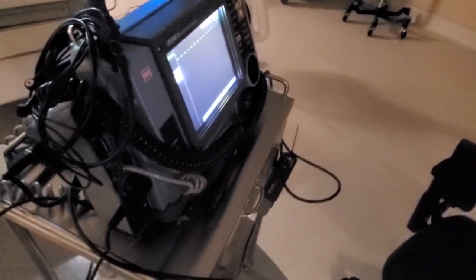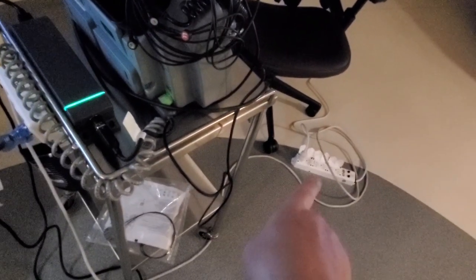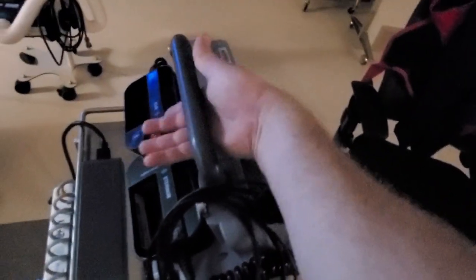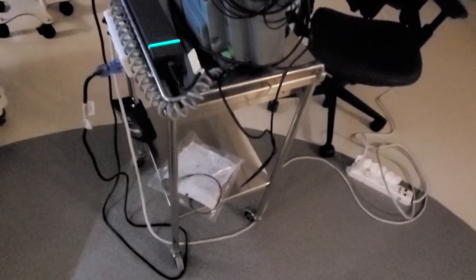Now over here we have a defib. One of the things you want is a defib to be rapidly deployable. Look at how the leads are just kind of thrown up here — they should be neatly wound and stowed so you can just grab them and use them. Also, if this unit lives on this cart with its power brick, this cord will come unplugged because of the way it comes up and over. And people don't even realize it — that's bad.